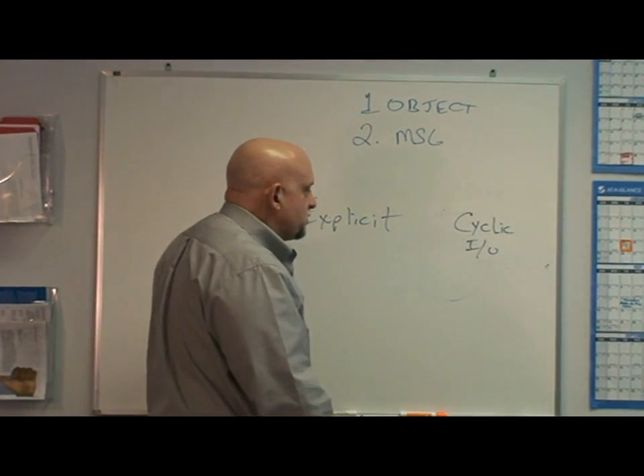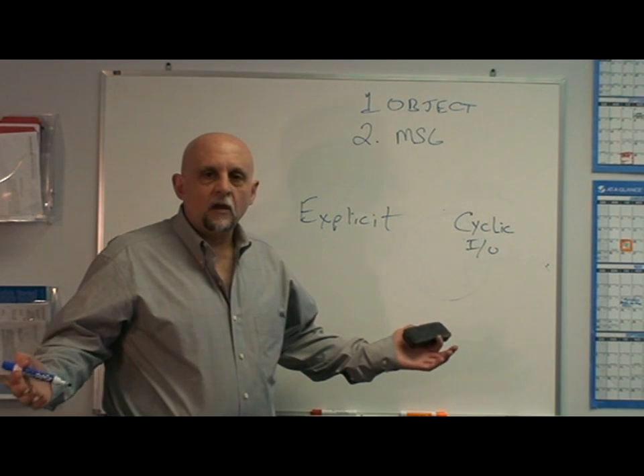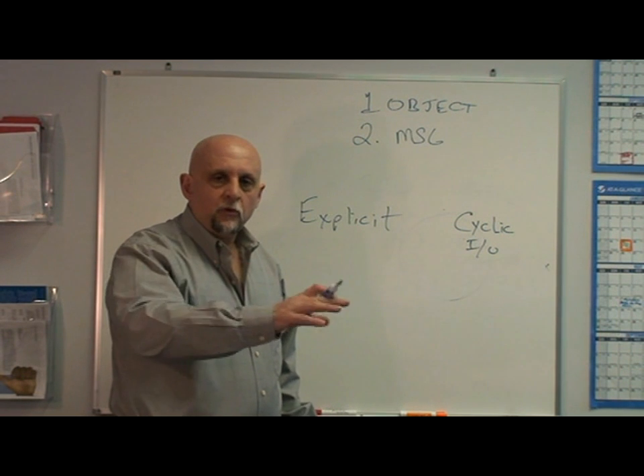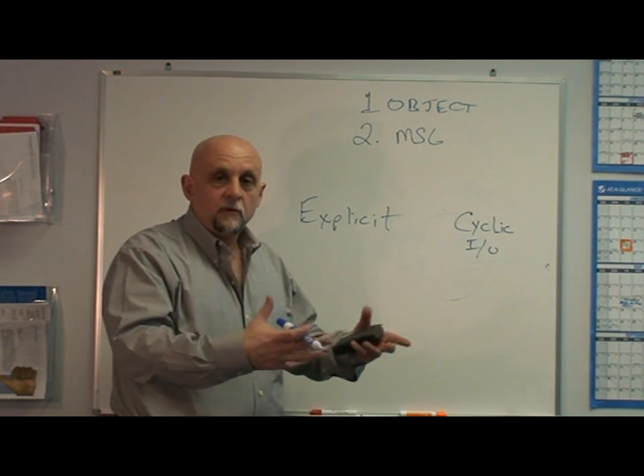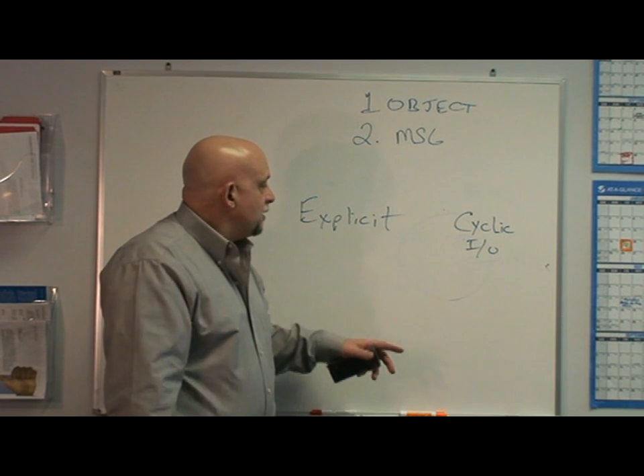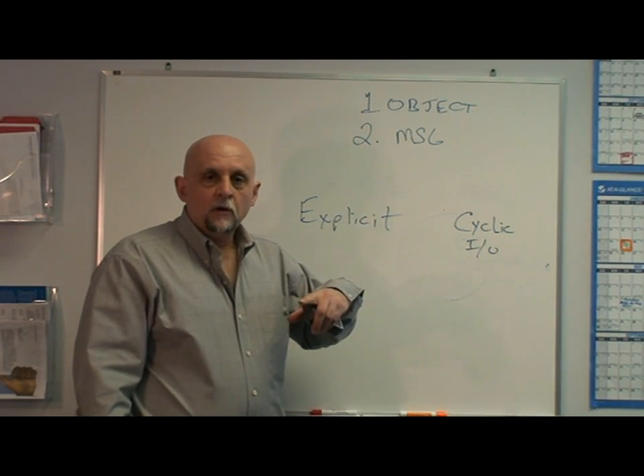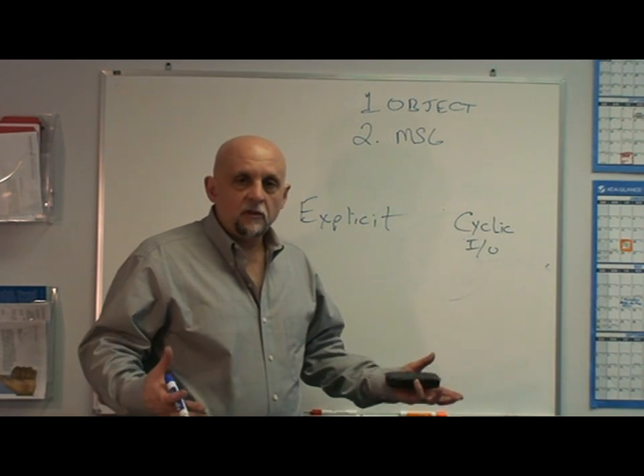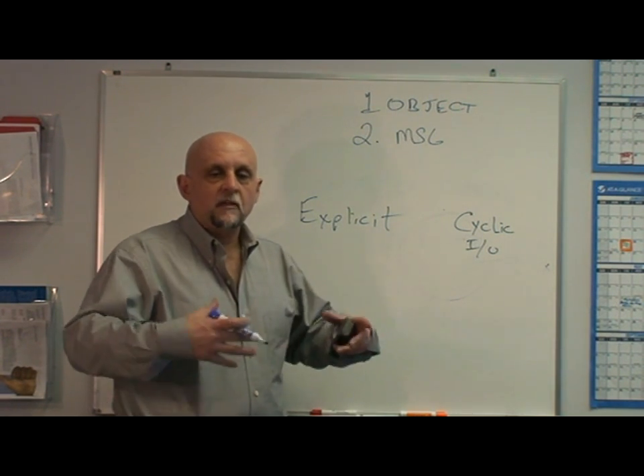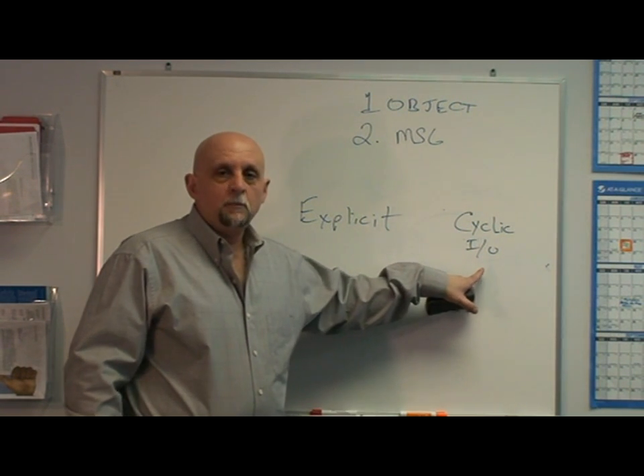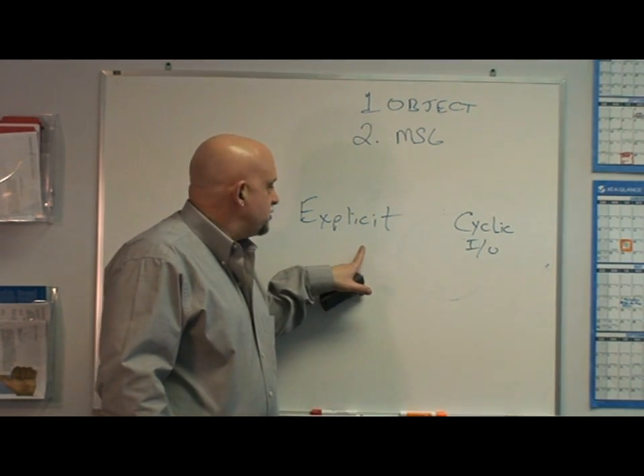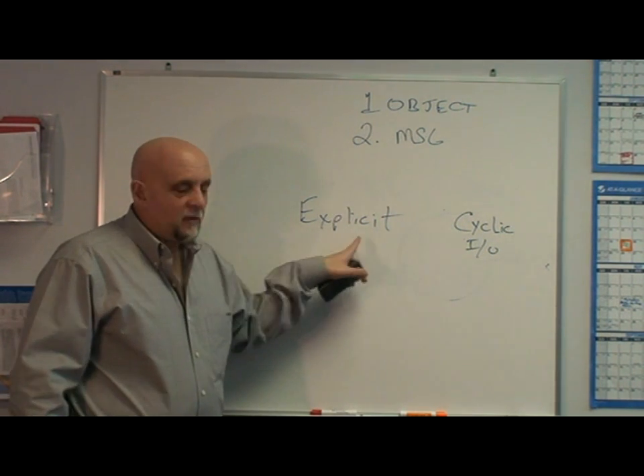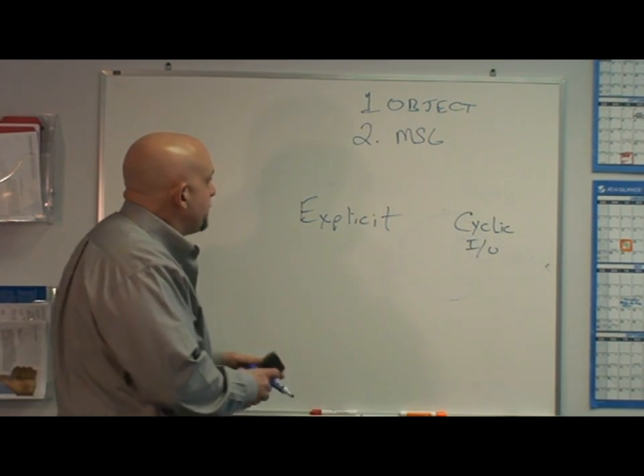An I/O message, on the other hand, is just bits. Both sides have to understand the contents of those bits. The PLC sends outputs out to the device, the device knows what every bit in that packet means. The device sends data back to the PLC, and the PLC knows what every bit means. There's no header information, nothing to indicate what that data is — they both mutually understand it. It's also called implicit data, to distinguish it from explicit data. Those two message types are the second thing you have to know.